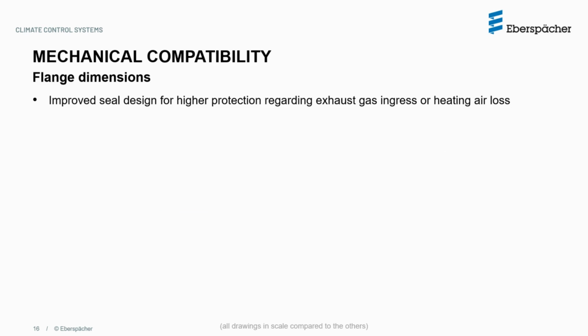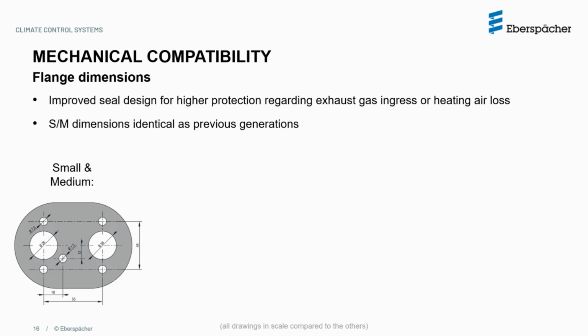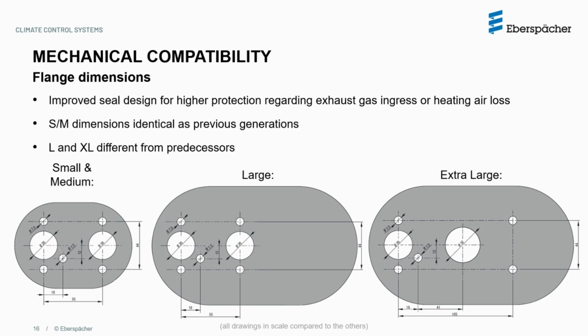Regarding the flanges, the seal design has been improved for a higher protection on exhaust gas ingress and heating air loss. For the small and medium sizes, the dimensions of the flanges and bolt and stud measurements are identical between each other and also the same compared to previous generations. On the other hand, just like the heater dimensions, the large and extra large flanges are different from their predecessors. You can see that the bolt and stud measurements are the same between small, medium, and large sizes, but the flange area is much larger on a large size. The flange area is the same between large and extra large sizes, but extra large has different bolt and stud measurements. Knowing this might be useful if you're considering changing sizes of heaters in an already installed application.